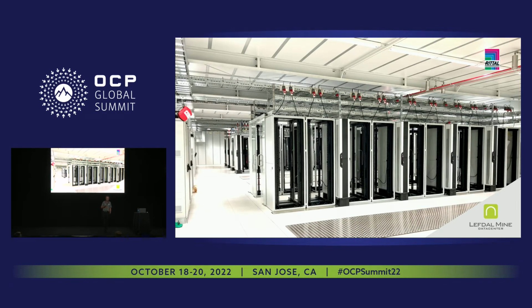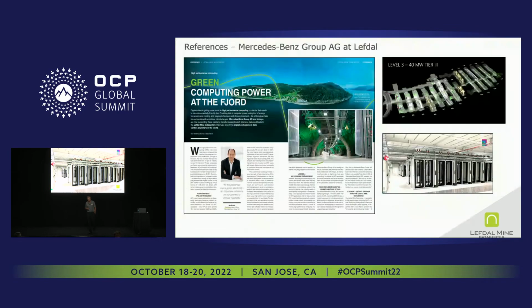This is an internal view of such a data hall. You see the modular structure of the room panels with a steel supporting structure. Within that room, we just built a classical hot aisle, cold aisle containment. In this case, you see a liquid cooling technology that we use at the customer. But as mentioned, CRAC units or any other type of cooling is also possible in this location.